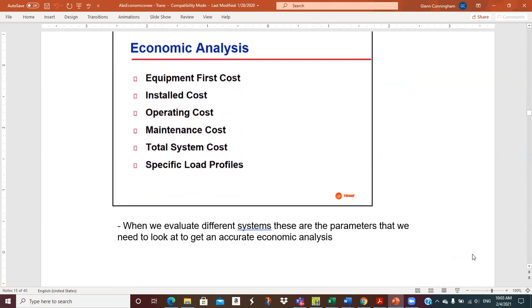So in the economic analysis, it's funny, in engineering we like to do BTUs or energy flows or stresses or strains or PSI, whatever. But out there in the world, it's the dollars. Everything eventually gets translated back into dollars, and that's where the decisions are made. So being good at the cost analysis, the economic analysis, is a huge skill. The things included in this are the first equipment cost: how much does it cost to buy one type of chiller versus another? Absorption are a little more expensive. Install cost, is there a difference? Operating cost, maintenance cost, total system cost, and then specific load profiles that, if we can conjure up the right one, might make this absorption look economically attractive.